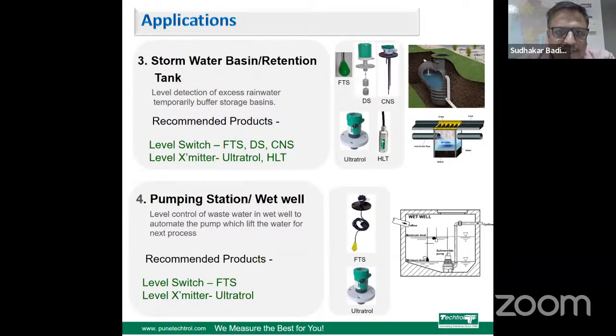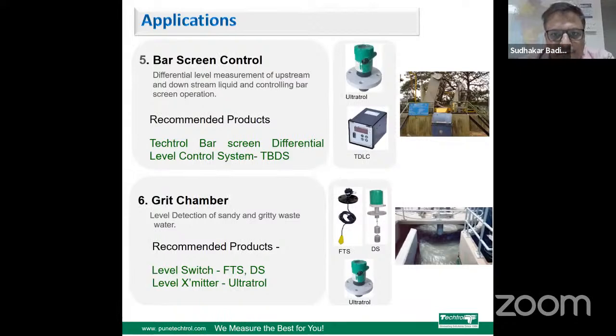Then stormwater basins and retention tanks, where we can use displacer type and float type switches and conductivity switches, and in transmitters we can use hydrostatic and ultrasonic level transmitters. For pumping stations and wet wells, for the inlet wet wells, we have monitoring with ultrasonic level transmitters, and even hydrostatic level transmitters with proper protections. Then we use switches like tilt type switches. Bar screen control we have already explained; here again, the ultrasonic level transmitters and controllers. For grit chambers, we have float type switches like displacer, tilt type switches, and Ultratrol level transmitters.